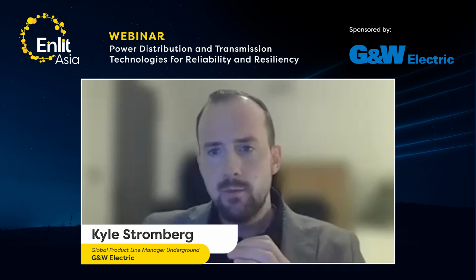Over time, we've seen a push from the industry to move away from technologies like SF6 that have a negative environmental impact. So for several decades, we've been building out a solid dielectric insulated portfolio for underground connected applications. One thing we do with this portfolio, as John hammered in his intro, is emphasize customization capabilities. In North America, there are diverse locations where cables may be buried underground, but the real estate available to connect switchgear devices to those cables varies greatly depending on geography, whether it's an urban or rural area.